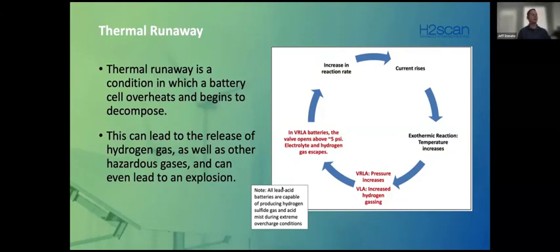You're going to release a lot of hydrogen. And if the battery continues to be charged, it simply won't cool down, and it goes into an overcharged condition. If you've ever heard of a battery smelling like rotten eggs, what you're smelling is hydrogen sulfide, where two hydrogen atoms combine with a sulfur atom. Hydrogen is lighter than air, so it rises towards the ceiling, but hydrogen sulfide is heavier than air, so it goes towards the floor, kind of like propane. In any case, we are trying to avoid any thermal runaway situation, as well as dangerous accumulation of hydrogen, and the production of hydrogen sulfide in an overcharged situation.